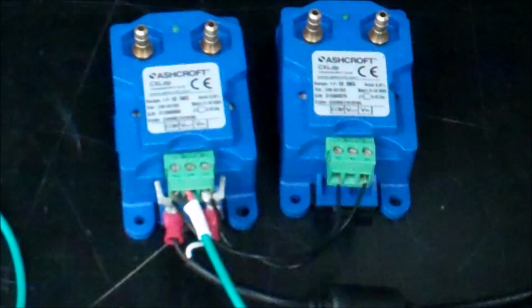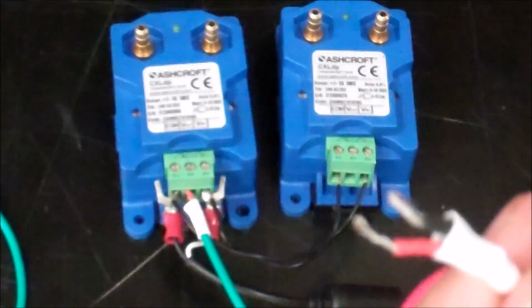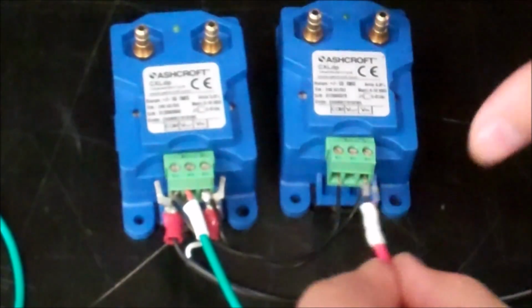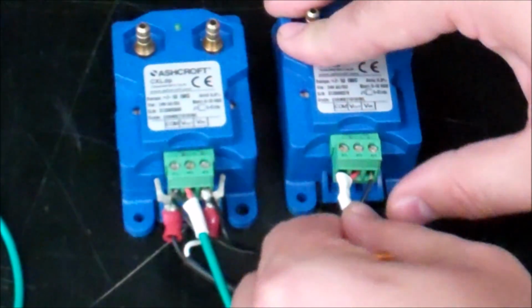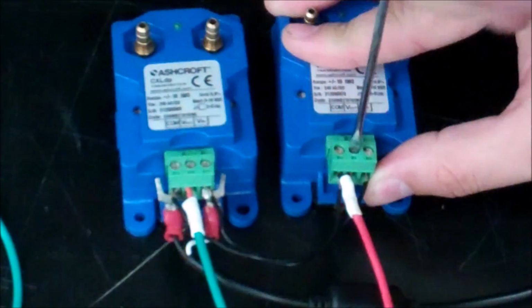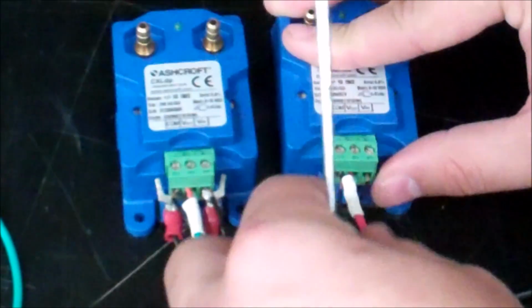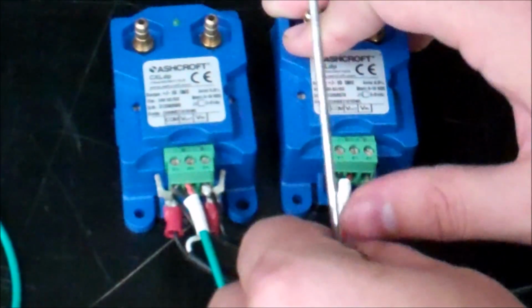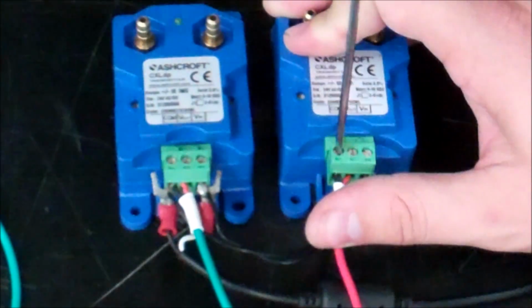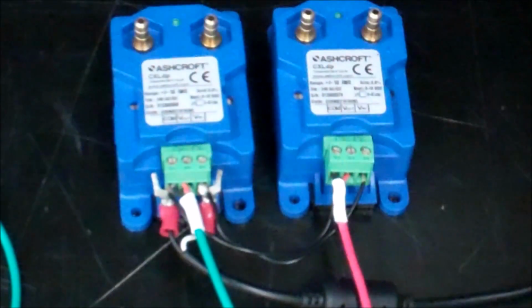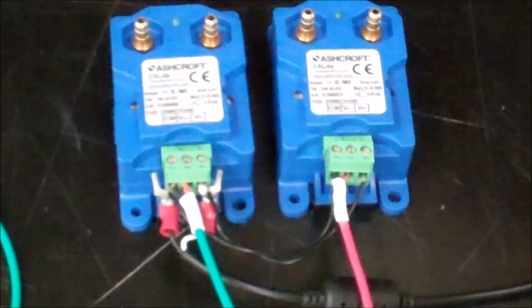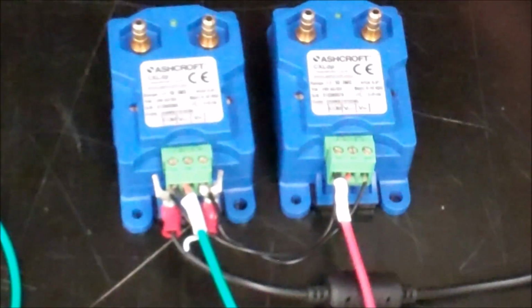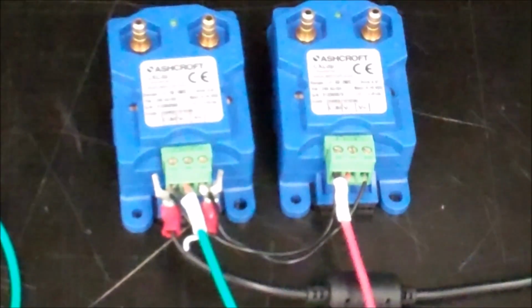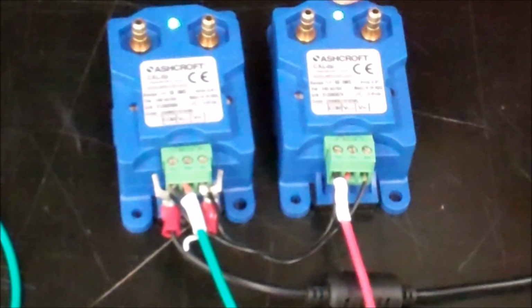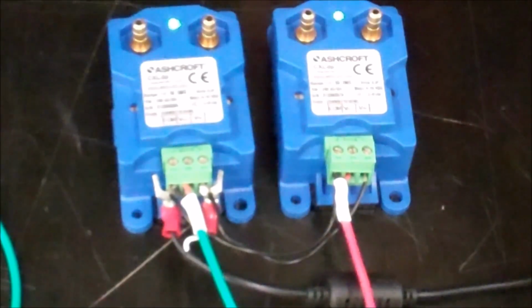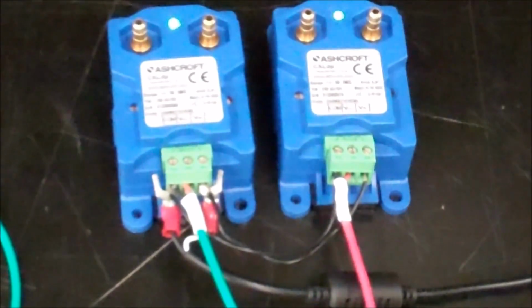And then on my second pressure transducer, I'm going to take my other BNC2 wire and I'm going to hook the black into the COM and the red into the V out. Go ahead and tighten the V out first. Make sure both sets of wires are on the COM side and go ahead and tighten those. And once you have all that connected, go ahead and make sure that both pressure transducers have power by plugging in the power adapter. And you can see here that both pressure transducers have their lights on, meaning that they have been connected successfully.